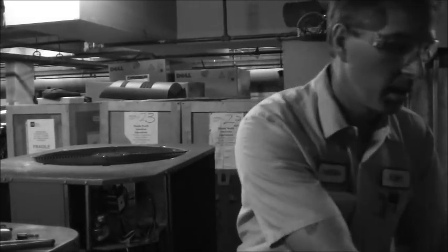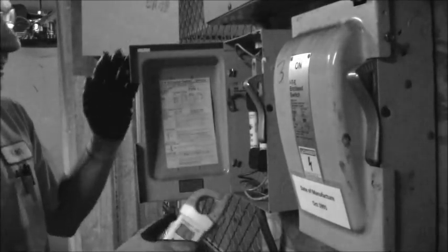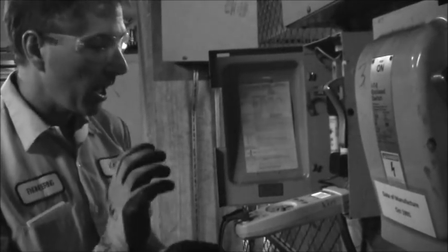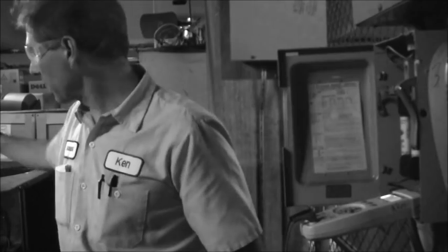So what I did is I took my meter, I put it on amperage AC, which is that setting right there. I opened up my disconnect, I put it on a phase like so, and then while I was standing off to the side, I turned the unit on. When I turned it on, the only thing that came on was the condenser fan motor. And the amperage jumped up high. But the only thing that it was rotating was the condenser fan motor, telling me that the compressor was locked. It was in a locked condition and it was not going to release.